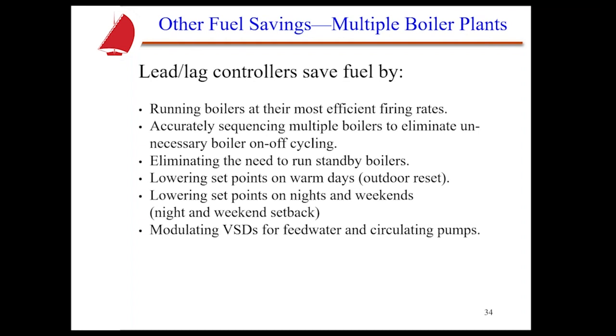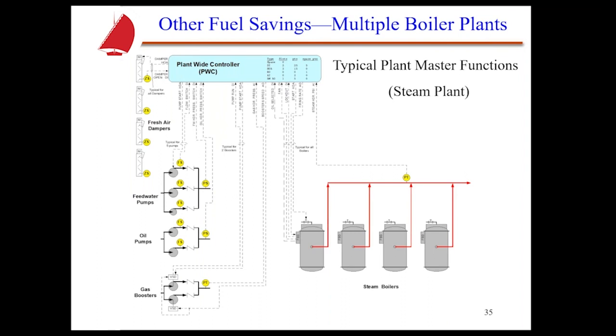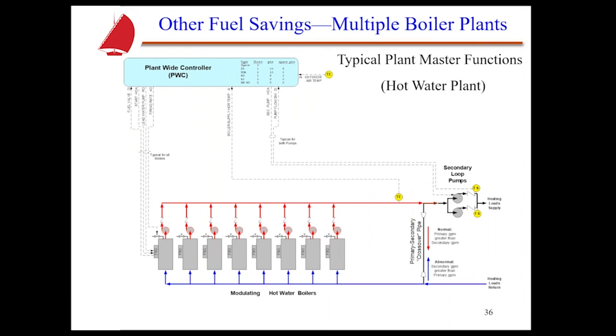A lot of the parallel positioning systems have this type of capability built in, but you don't get the full-blown capability as you would from, for instance, a plant master control like we offer. Many times that external device is so much better, and end users like them so much better. They just work. And of course, it can come into also modulating the VFDs for feed water and circulating pumps too. So look at the lead lag or sequencing requirements in a particular boiler room, and you're probably going to be best served by an external device, like our plant-wide controller. And this is just a diagram that shows you all the capability of our PWC and what it can actually do. It just gives you a lot more flexibility, a lot more control of that particular steam plant, or a hot water plant, same thing.